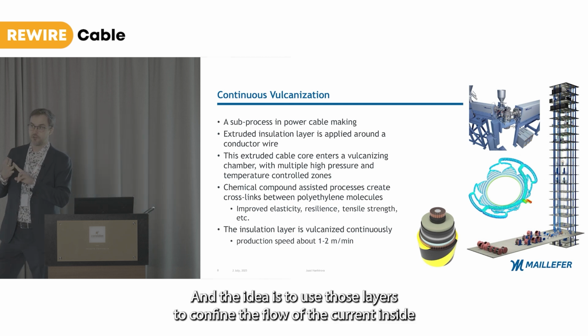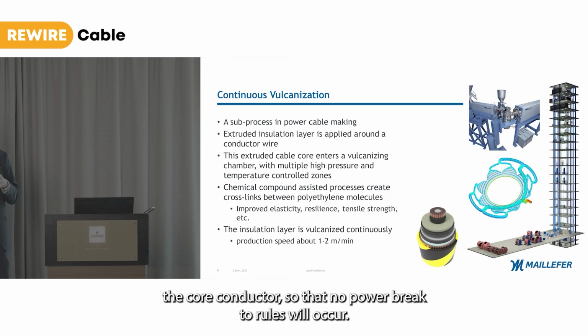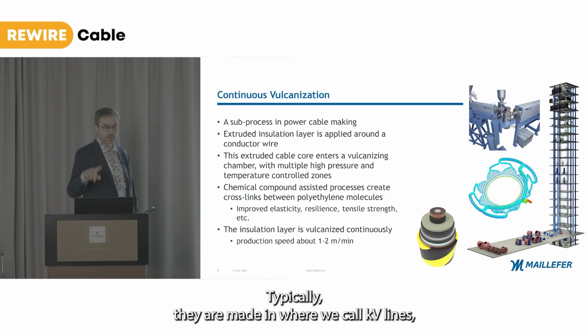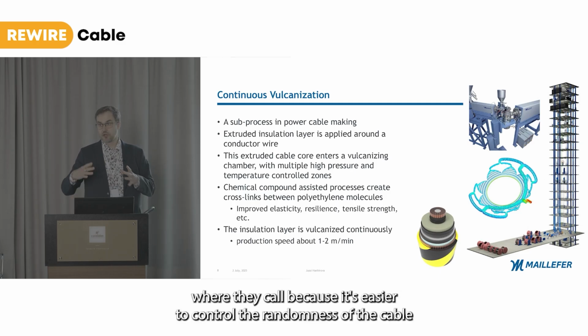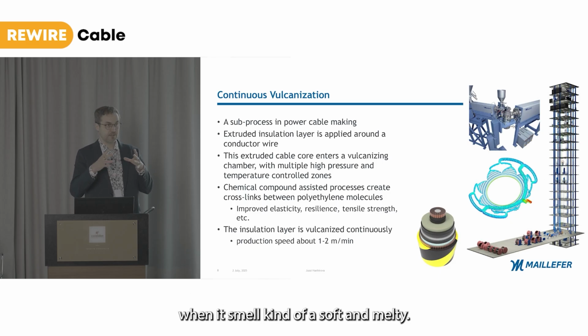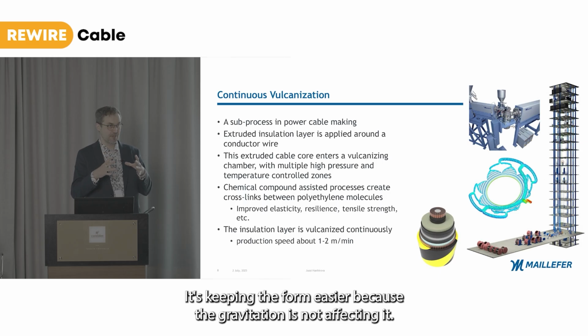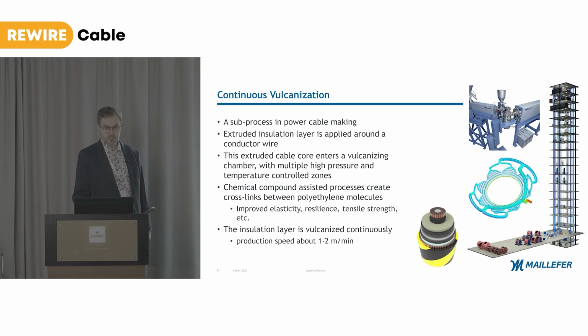The idea is to use those layers to confine the flow of current inside the conductor so that no power breakthroughs will occur. Typically they are made in vertical CV lines - vertical because it's easier to control the roundness of the cable. When it's soft and melty, it keeps its form more easily because gravitation isn't affecting it.